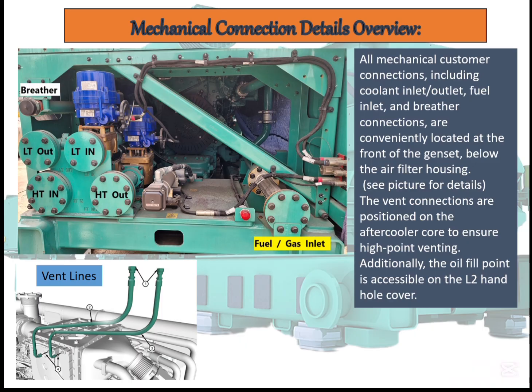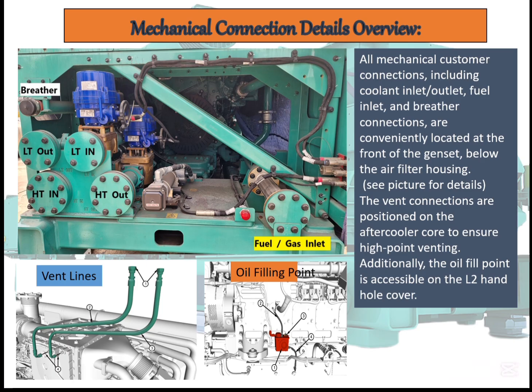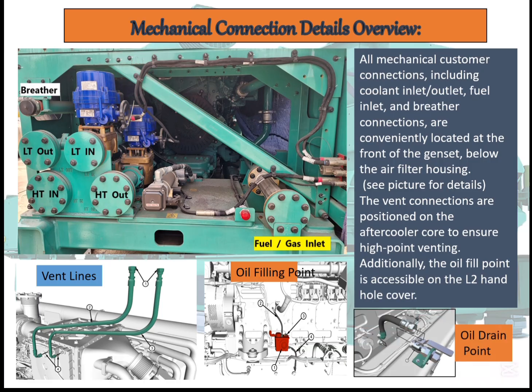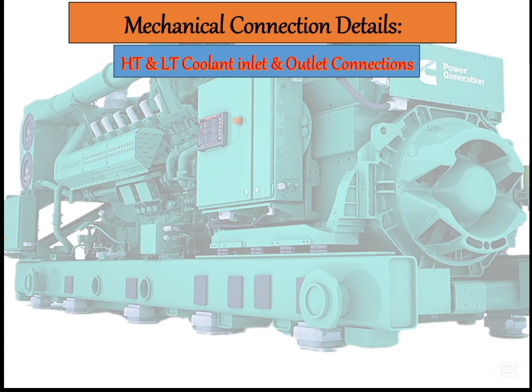Then we can look at the vent lines. The vent lines for cooling, LT and HT, are located at the highest point of the genset, that is the aftercooler core. Then the oil filling is located at the left side, an access cover where we can fill lube oil manually or automatically. Then the drain is also located on the left side of the genset. So let's have a detailed look at all these connections. The first thing we look at is the LT and HT coolant inlet and outlet lines.